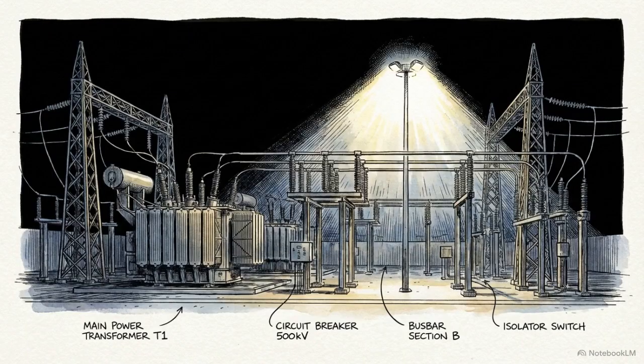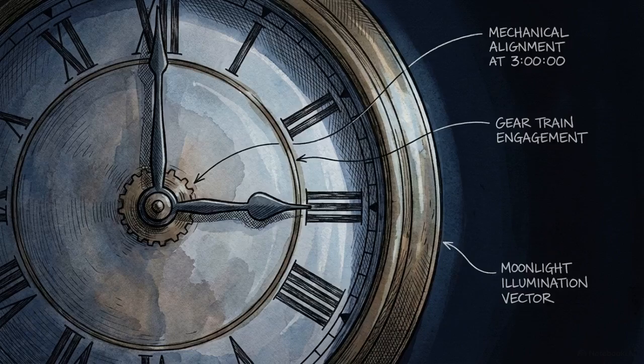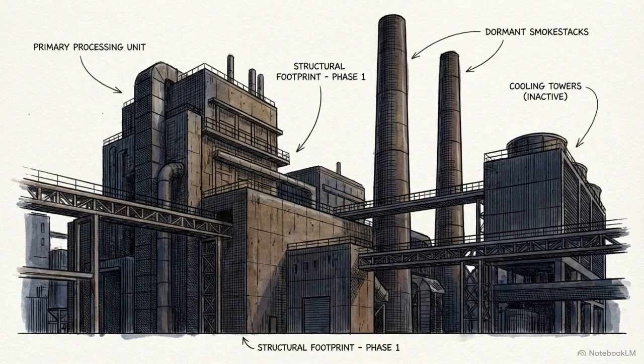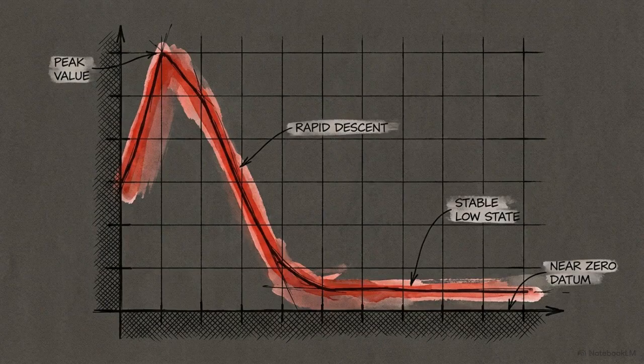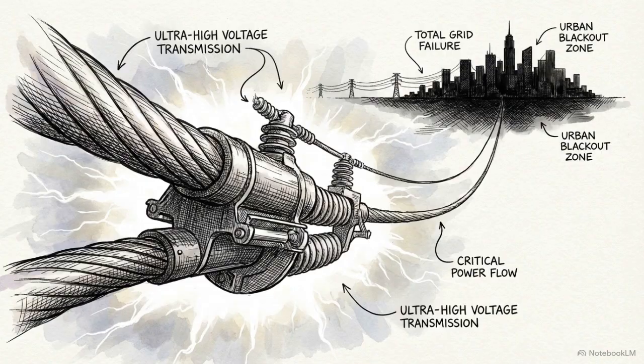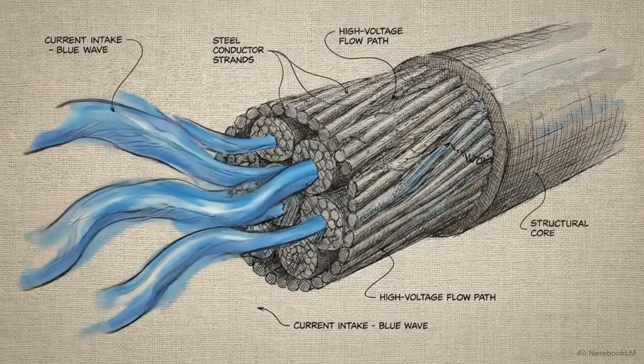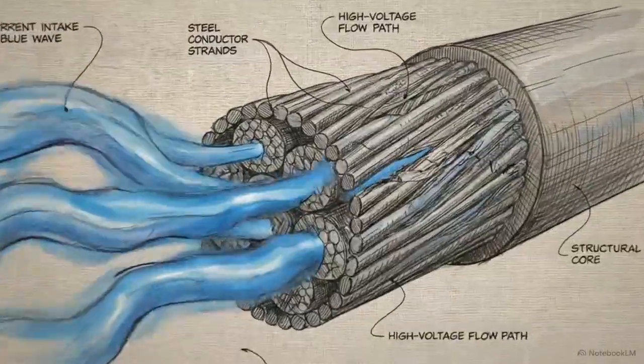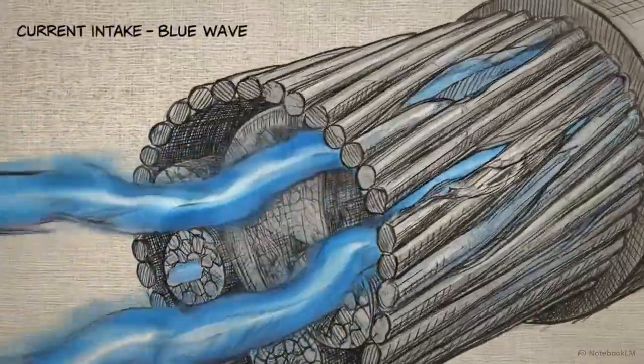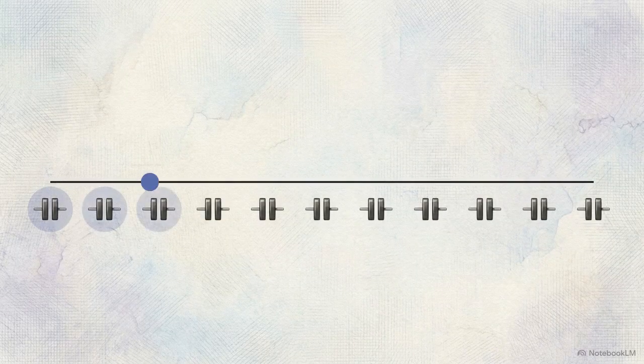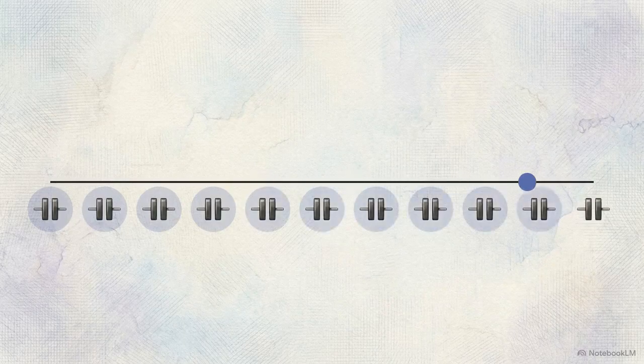The danger peaks deep in the night. Around 3 a.m., factories are quiet. Homes are dark. Demand drops to near zero. The line is fully energized, but the load is incredibly light. Even without customer demand pulling power, a baseline flow of electricity called a charging current must continuously enter the line. This charging current exists for one reason: to satisfy the massive distributed capacitance of the hundreds of miles of wire.